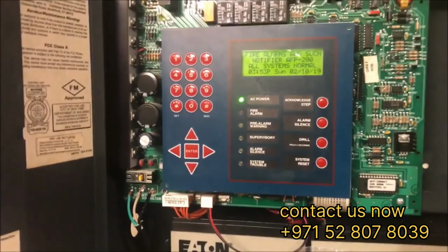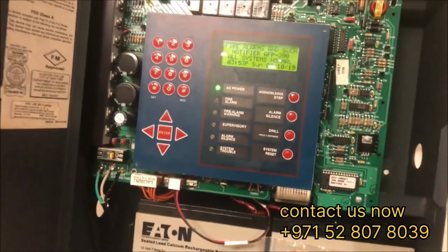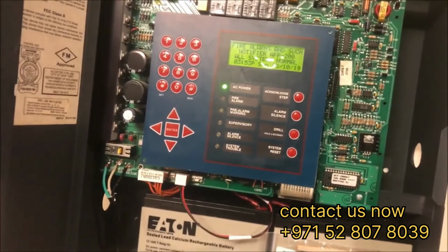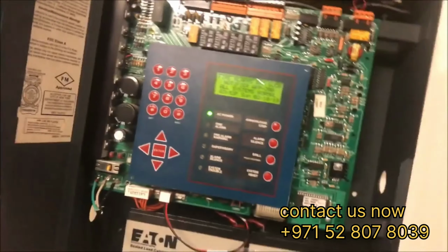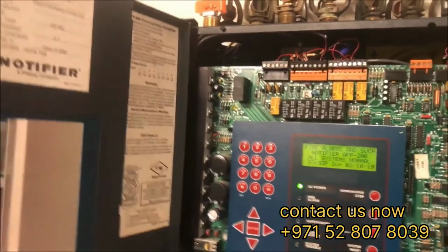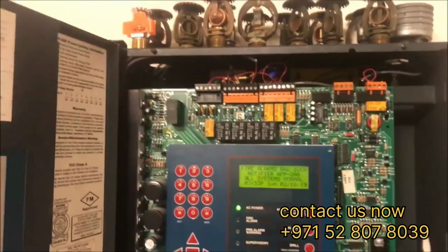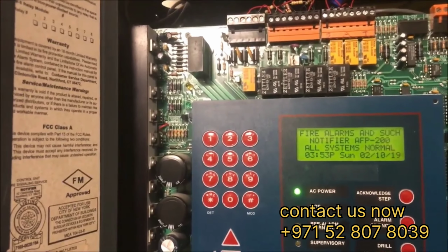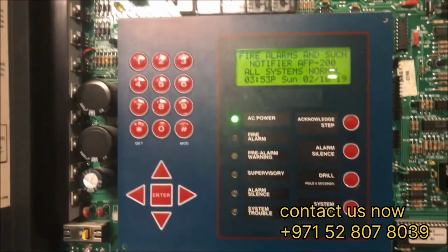This one is listening for the module to talk to it about what's happening right exactly now. It's listening to all those different frequencies. And these ones you don't have to supervise with a resistor. Now again, that's up to different codes, but these ones you don't have to, because it's only listening for a module. So if the module's not talking back, you know, okay, I'm not hearing you anymore, something's wrong.